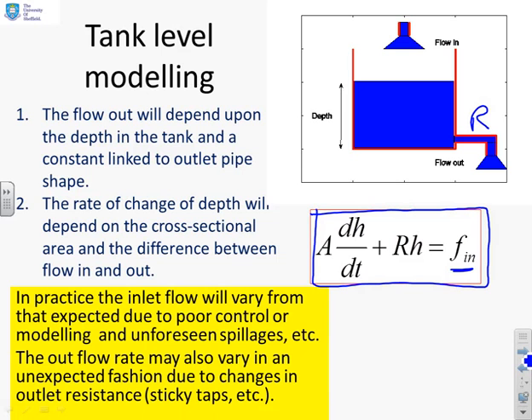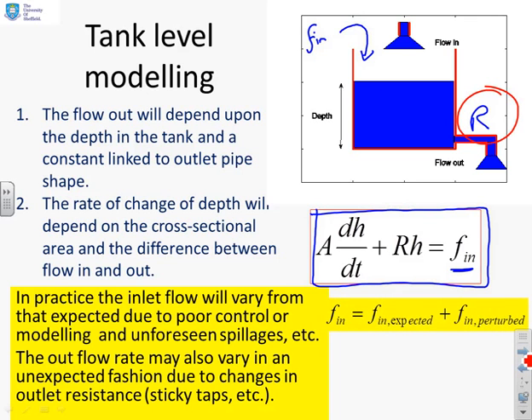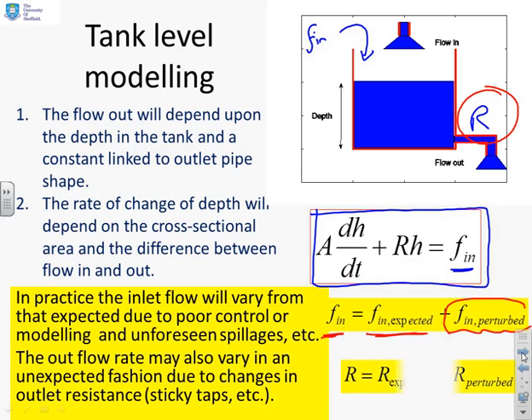In practice however, we're going to say there may be an extra flow in coming in from the side or from somewhere else. The inlet flow suffers perturbations and it could be due to poor control of the flow in, poor modelling, or unforeseen spillages coming into the system. Also, the outflow rate is going to vary because of changes in this R. The reason this R could change could be temporary blockages in the pipe, temporary stiction, sticky taps, back pressure, and other issues.